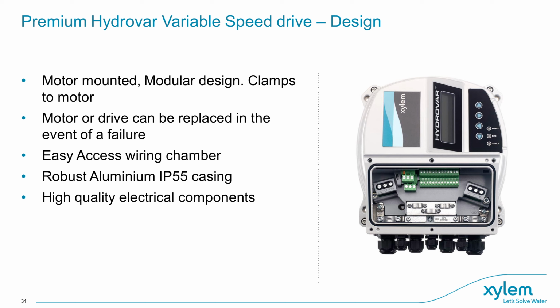And perhaps one of the biggest selling points is that it is a modular motor mounted drive. This means that if the drive was to fail for any reason, the drive could be swapped with another unit straight off the shelf. The drive and motor are separate and not specific to the pump. And the drive is motor mounted using 4 metal clamps that are easy to fit and can be done with just a screwdriver. No specific tools required.